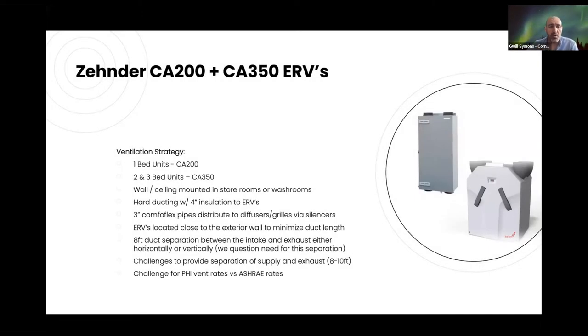The strategy uses Zehnder CA 200s for one-bed units and CA 350s for the larger two- and three-bed units, stored in washroom or storeroom ceilings. Hard ducting to the exterior uses four inches of insulation, and three-inch ComfoFlex pipes distribute within the suites via drop ceilings. We have the typical challenge of trying to get the ideal eight to ten feet separation between supply and exhaust, and always hitting those Passive House ventilation rates while also making it work from an ASHRAE standpoint.